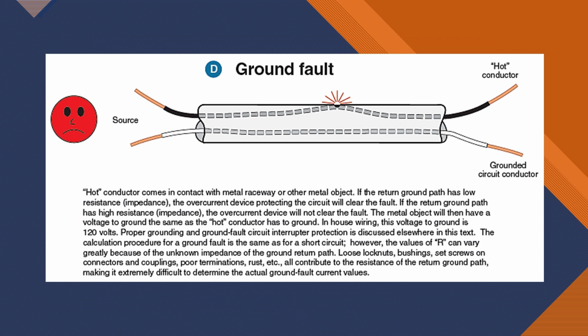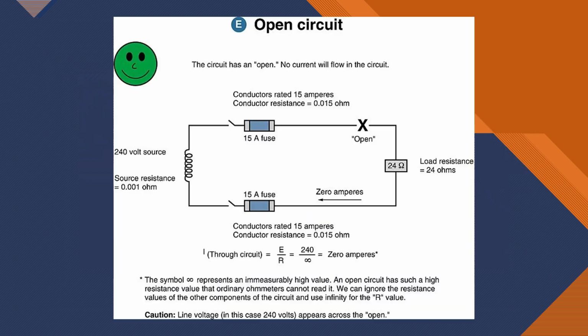If I have a ground fault and I'm in the thousands of amps, what happens? A ground fault, same thing. I have a hot conductor somehow touching or going to something that's grounded. I have an open circuit. I pretty much have infinite resistance. It's just infinite resistance, and therefore I have no current because, again, current is inversely proportional to resistance.